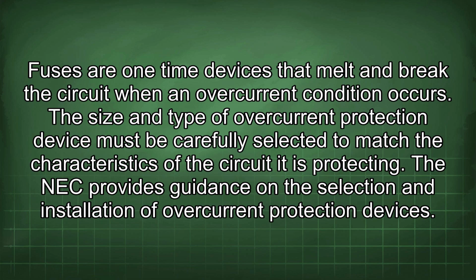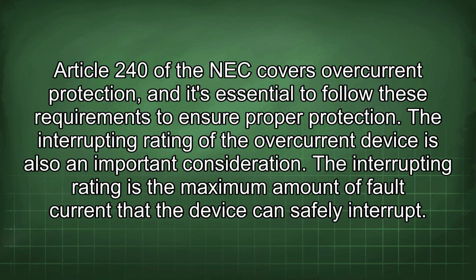The size and type of overcurrent protection device must be carefully selected to match the characteristics of the circuit it is protecting. The NEC provides guidance on the selection and installation of overcurrent protection devices. Article 240 of the NEC covers overcurrent protection, and it's essential to follow these requirements to ensure proper protection. The interrupting rating of the overcurrent device is also an important consideration.